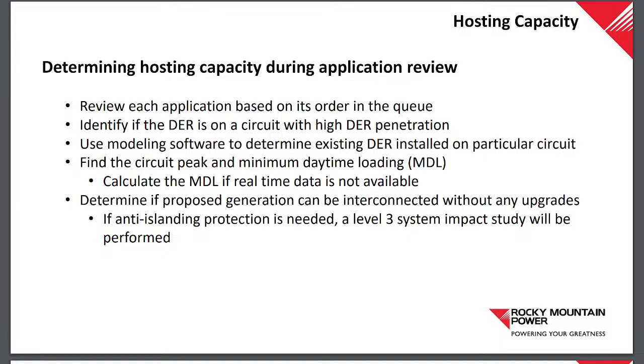Does that mean like you can't? Yeah, so anti-islanding is, and Jake might be able to better explain it than me, but basically when the generation to load is at 0 or the generation exceeds the load at the breaker and we're getting reverse flow and we have a fault or something happens, there's maintenance or something that causes that circuit breaker to open, we use high speed reclosing. So when you see the inverters, they're required to stop being energized within 2 seconds. But when we're closing in 10 cycles or 30 cycles, 0.3, 0.2 seconds, that's too soon for them to come offline. But if we see that there's more load than generation, when that circuit breaker opens, those generators aren't going to be able to support that load, and they go offline immediately.